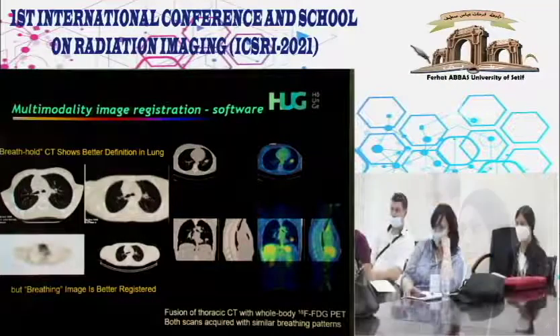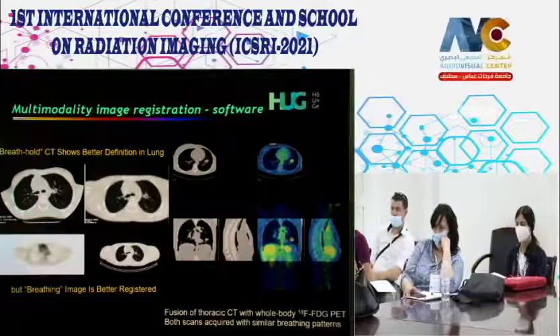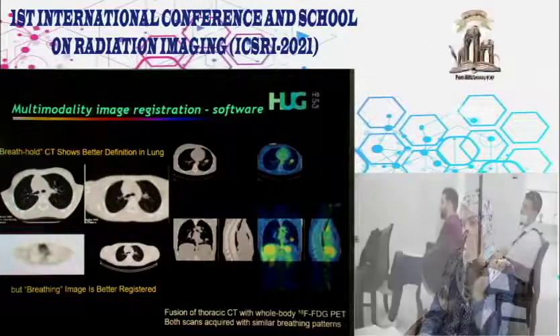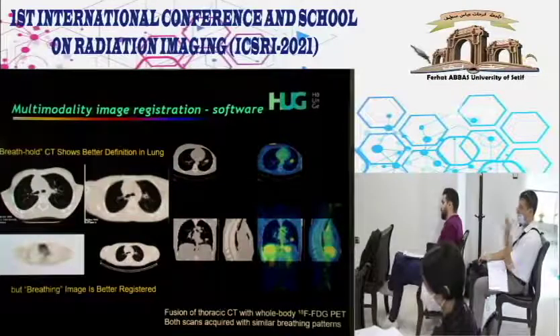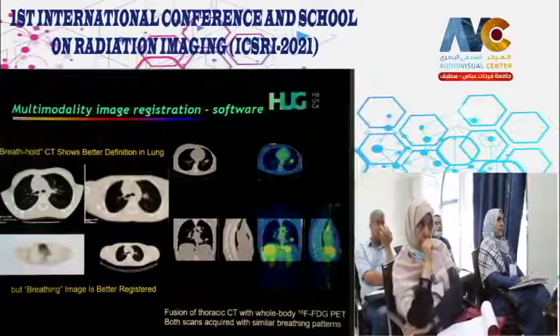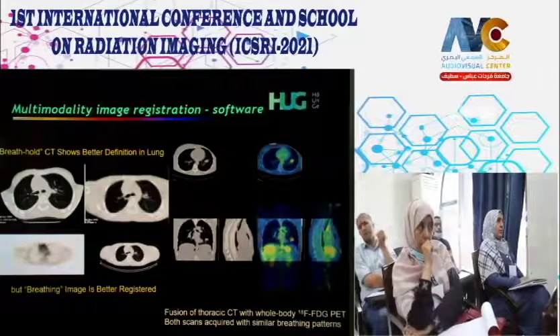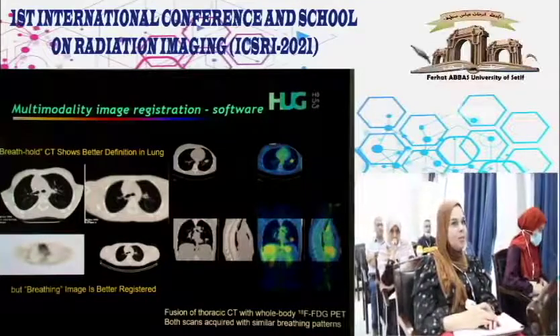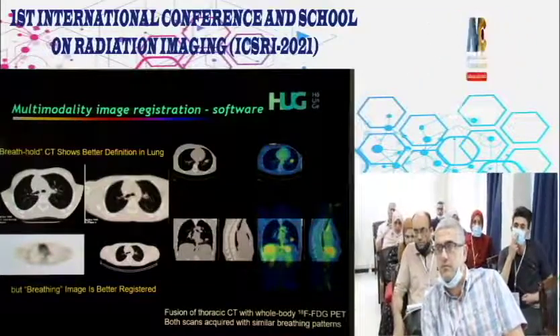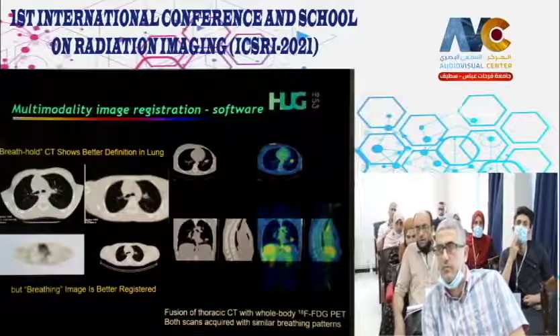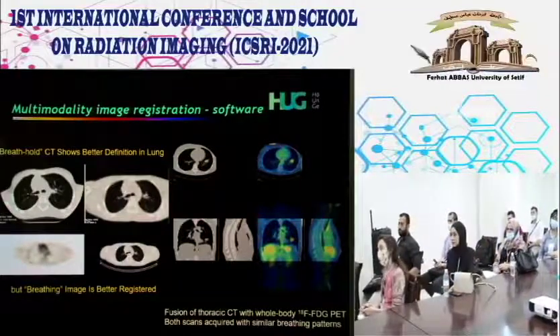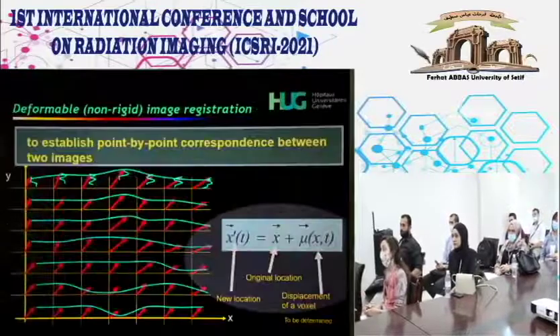Registration is extremely challenging in the thorax and upper abdomen: x-ray CT takes only a few seconds while PET takes 3–4 minutes, and differences in breathing patterns cause misregistration. Careful protocol adjustment can achieve good registration quality.